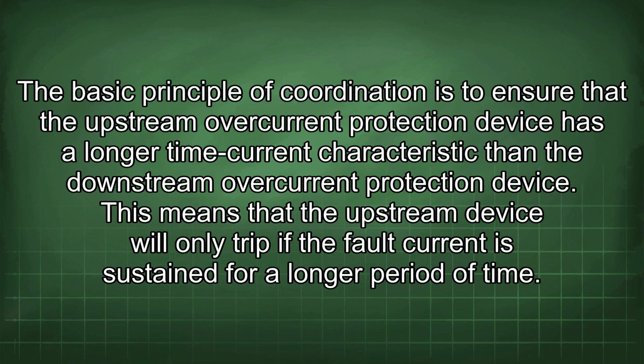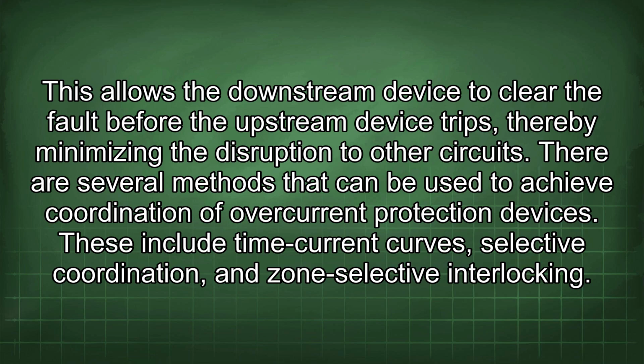The basic principle of coordination is to ensure that the upstream overcurrent protection device has a longer time current characteristic than the downstream overcurrent protection device. This means that the upstream device will only trip if the fault current is sustained for a longer period of time. This allows the downstream device to clear the fault before the upstream device trips, thereby minimizing the disruption to other circuits.